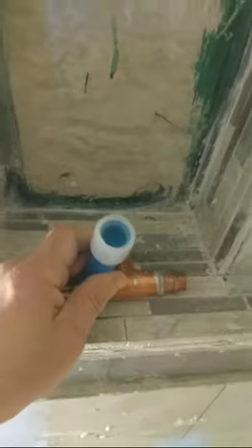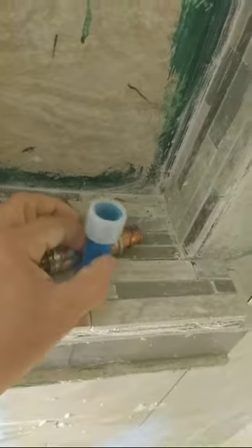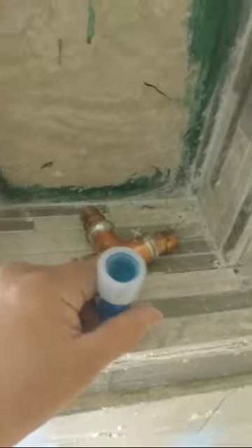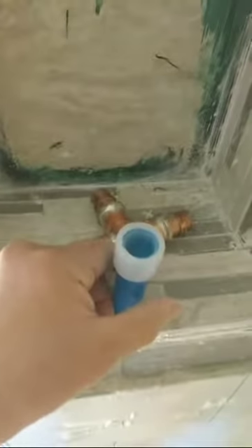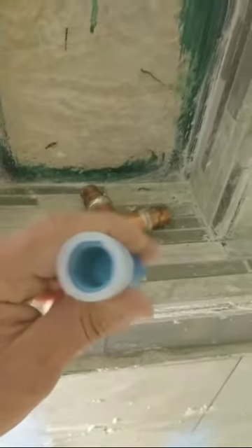The only issue with this, if you're doing anything with the PEX, is you make sure, because you've got to put a little bit of oil on the expander parts of it, because they open up, so you want the connection points lubricated with this grease. And if you get any grease in here, then it can cause it to drip. You have a little leakage. So make sure that your tool has a very small amount of lubrication on the metal parts of it that slip down inside here. So no oil enters into this area here when you expand it.